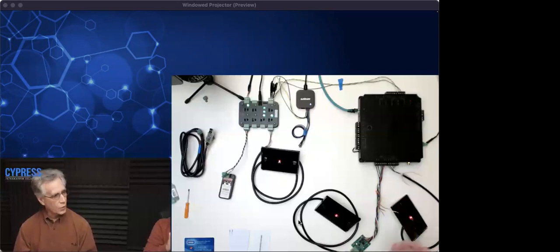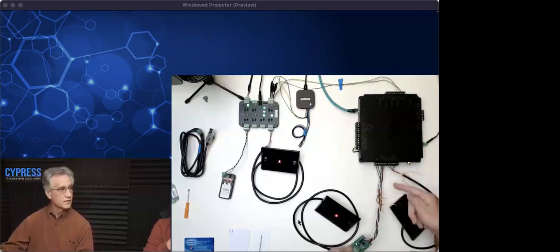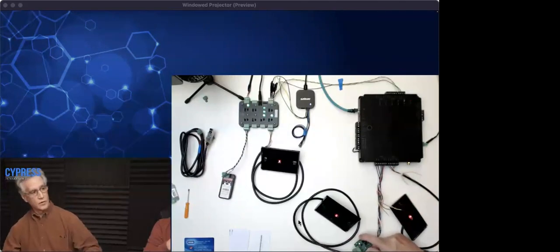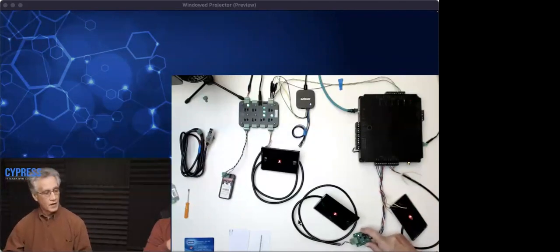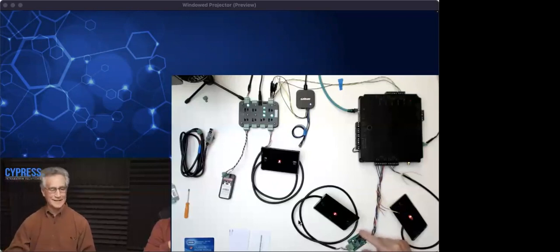So you're bringing that wire as close to, and in fact inside of, your access control panel. So it's a locked box in a mechanical room, and the Wiegand is there inside the panel box itself. So it's just this section of wire that is vulnerable to attack. From this connector all the way to your reader, I won't say invulnerable, in terms of maybe 1 trillion years it'll take you to crack that, but it is as secure as it needs to be.